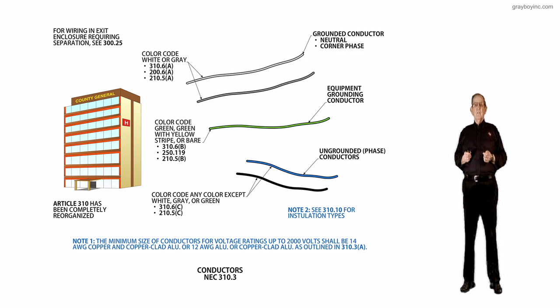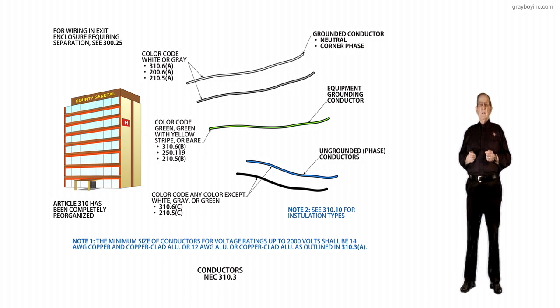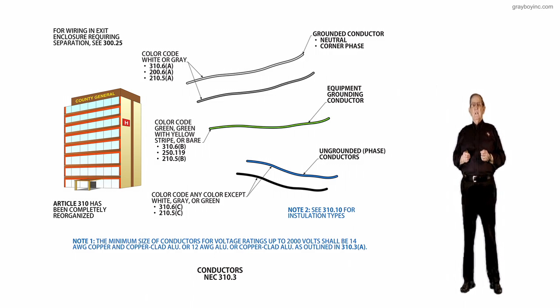A revision was made to clarify that the minimum size of conductors for voltage ratings up to and including 2,000 volts should be number 14 AWG copper and copper clad aluminum, or 12 AWG aluminum or copper clad, except as permitted elsewhere in the National Electrical Code.